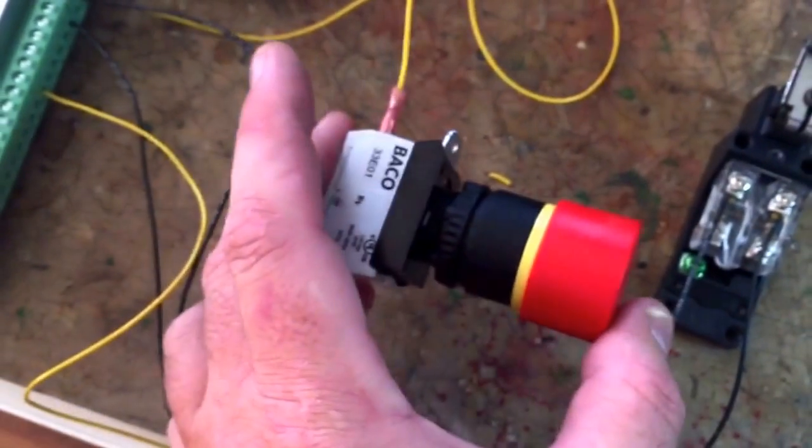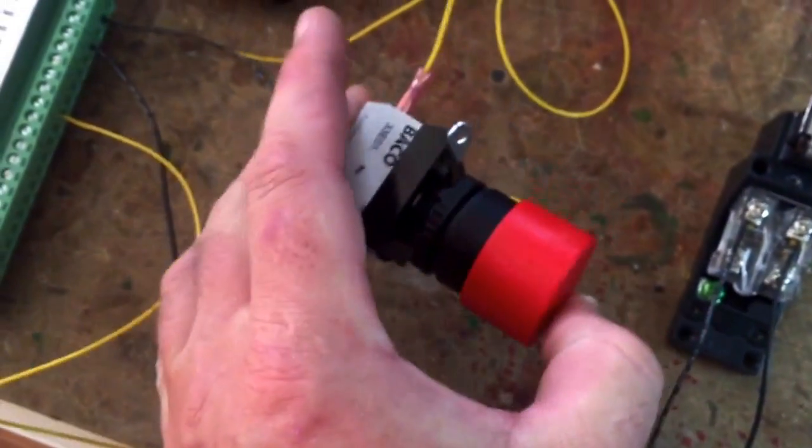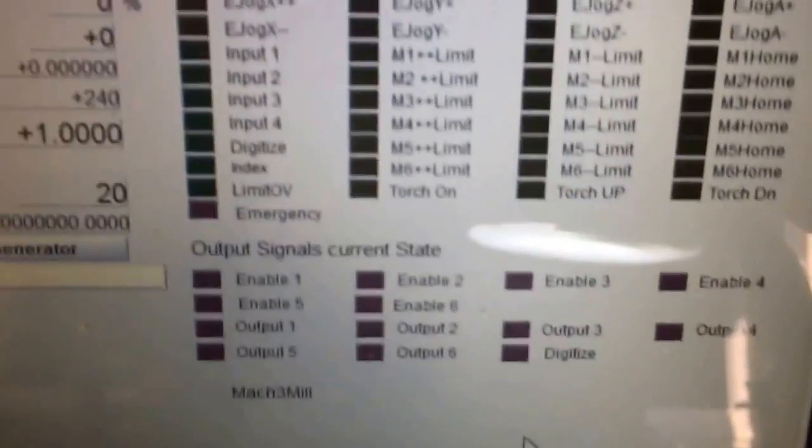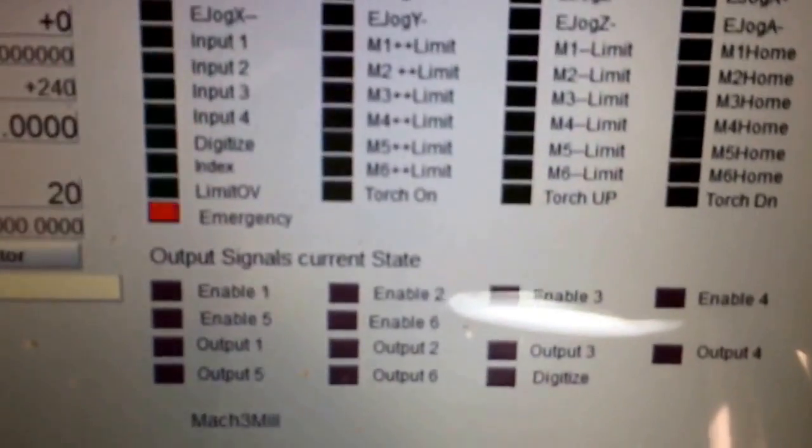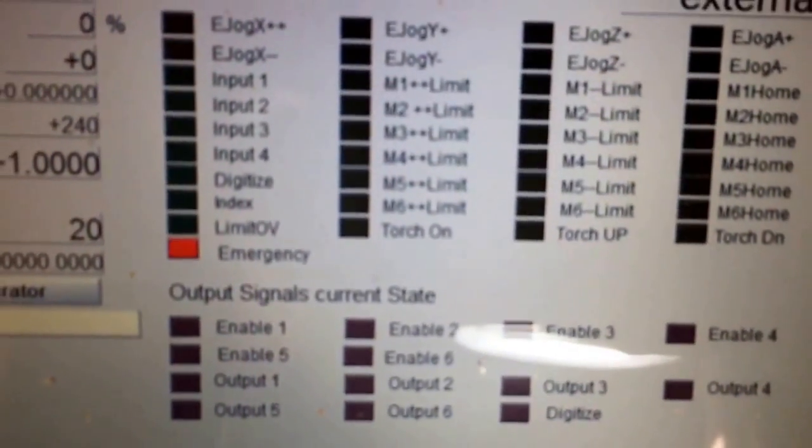So what I'll do here is here's the e-stop. Right now it's not an e-stop. So I'll press it in. Now that's enabled the e-stop alarm. Everything would stop in the controller. And you can see there's the signal from the e-stop switch flashing away.